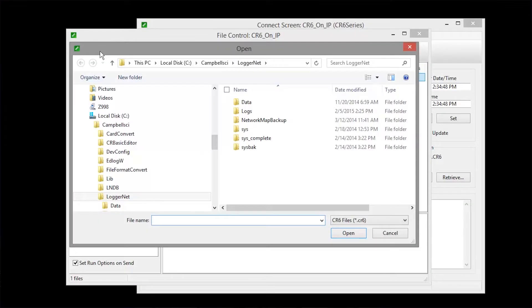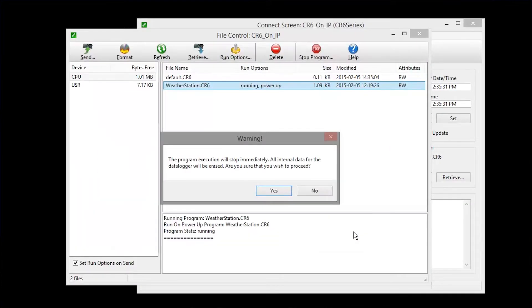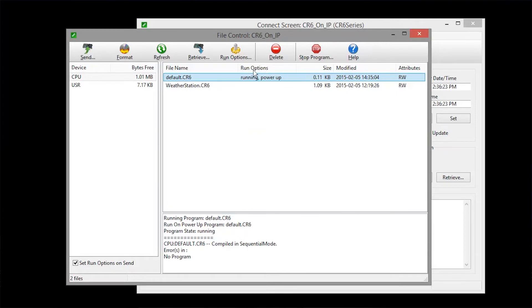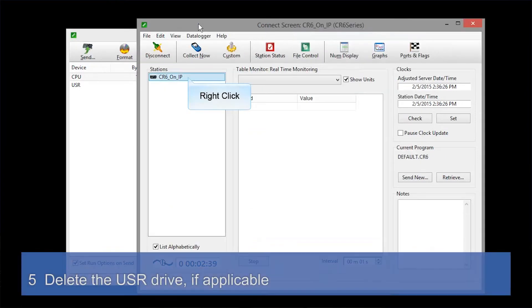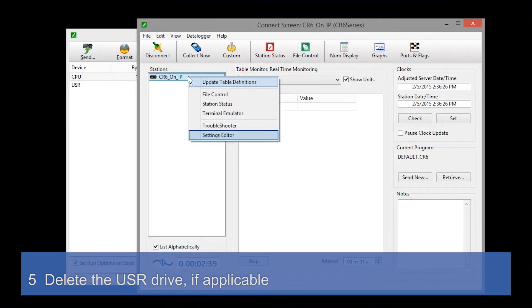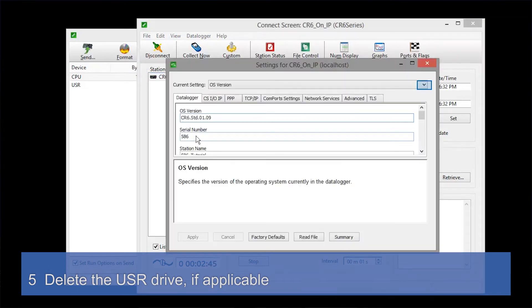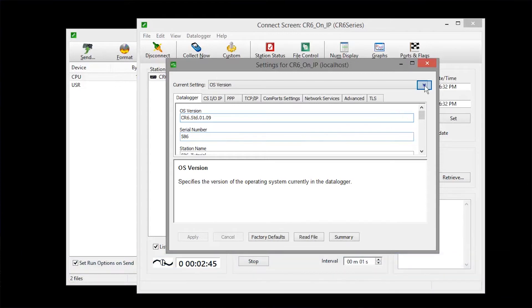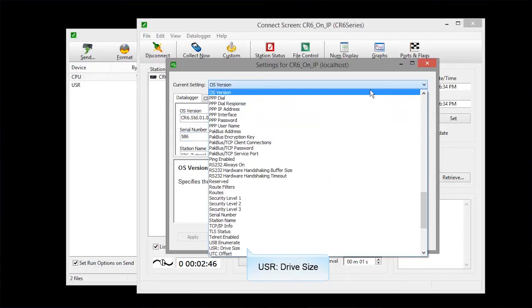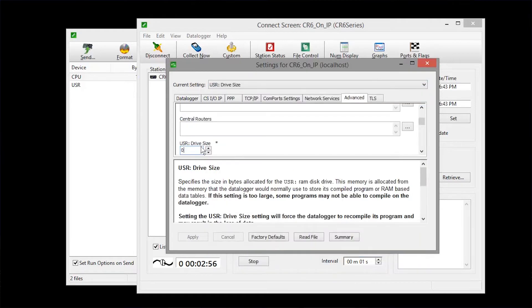Downloading operating systems over telecommunications requires much of the available data logger memory, so I don't have any instructions that would use memory, such as the data table instruction. We're okay here because we collected the data just a few minutes ago. Now let's go back to the Connect screen. Right-click on your data logger and click Settings Editor. This is a handy place to see settings and make basic changes. Use the drop-down to navigate to the settings you're interested in. We're going to free up more memory by setting the USR drive size to zero and apply those changes.